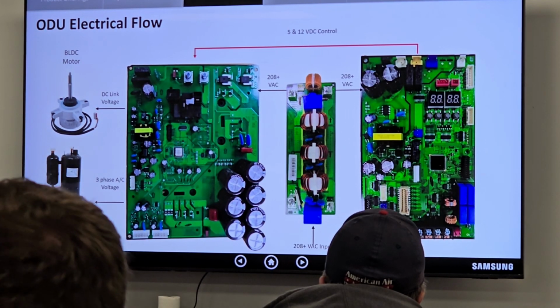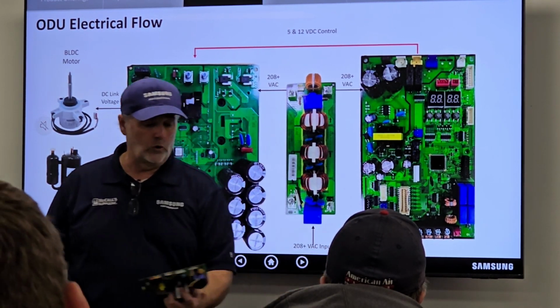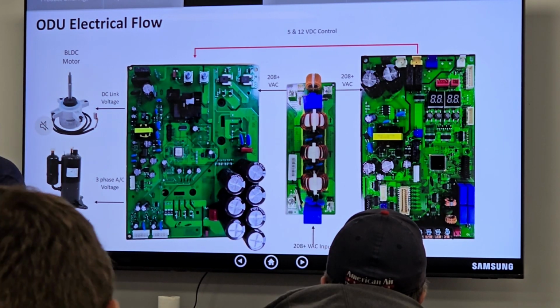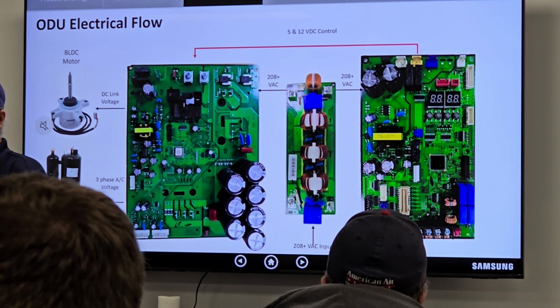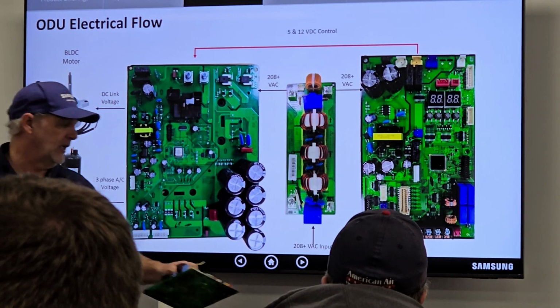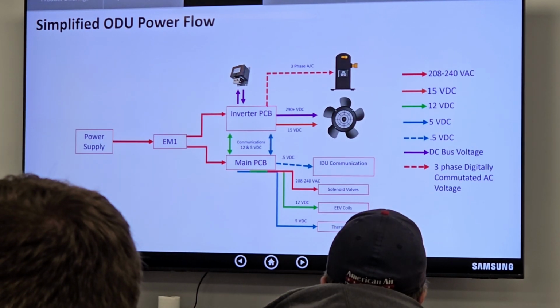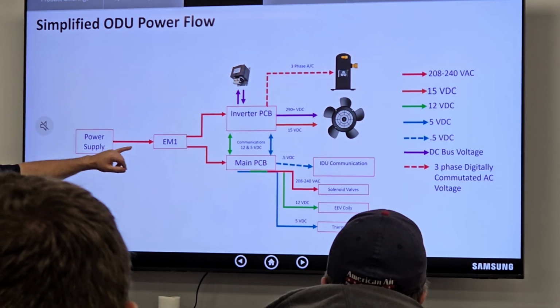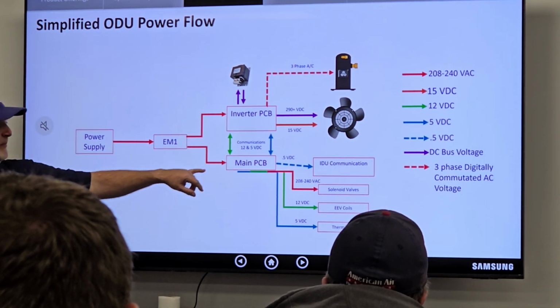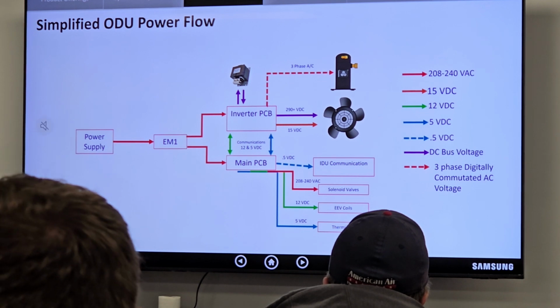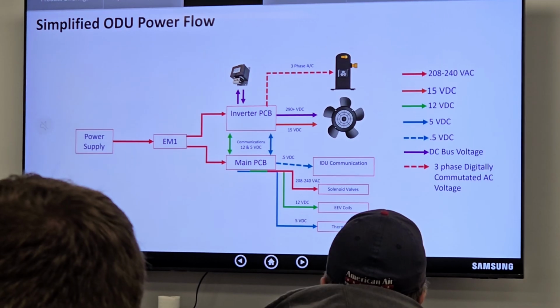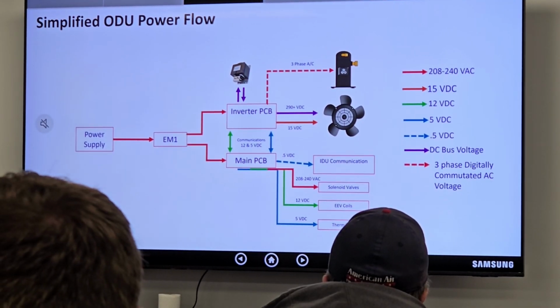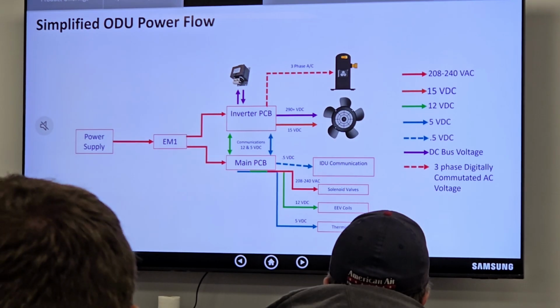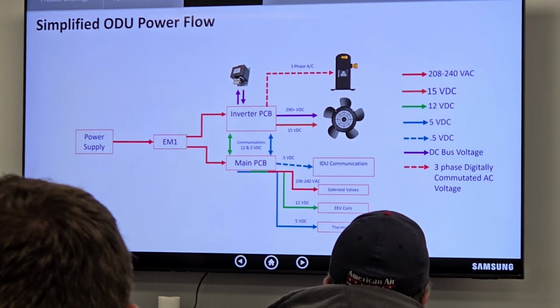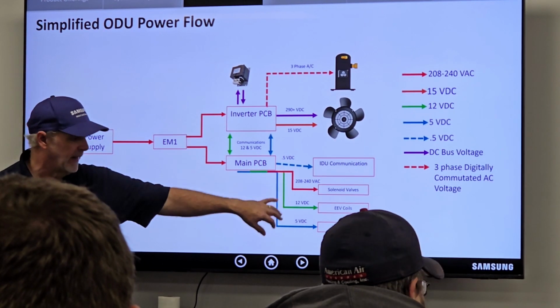On most products, if you look at the back of your inverter control board, there's going to be a red, green, and yellow light flashing in a sequence. And now we need to tell you where you find that sequence from there. But again, those are the types of things we deal with. So, power supply in, I clean it up, change it through the inverter to my DC voltage. My SMPS provides 12 and 5 volts DC for what? My EEV works off of 12 volts. My stepper motors for the blades on my heads work off of 12 volts as well. My thermistors work off of 5 volts or 3 volts, and so does my communication.